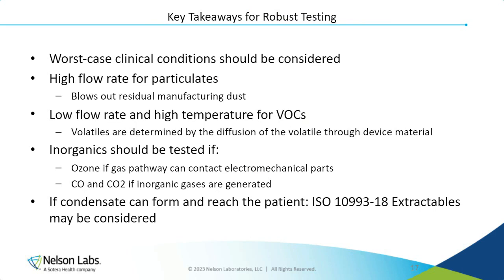The worst case clinical conditions must be considered. A high flow rate for particulates. We want to blow out all that residual manufacturing dust, capture and analyze it. A low flow rate and high temps for the VOCs. And inorganics if there are any electromechanical or just mechanical parts in general. If condensate can be formed and reach the patient, extractables and leachables must be considered using ISO 10993-18. And all of this testing can be done at our Nelson Labs locations.